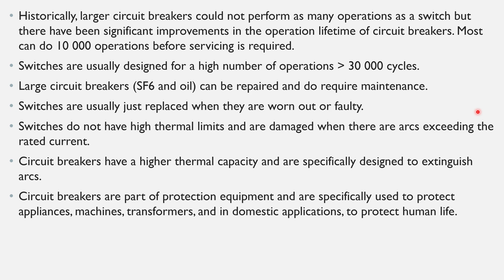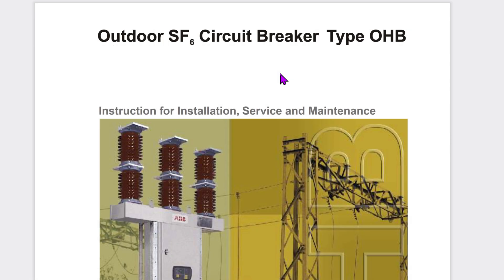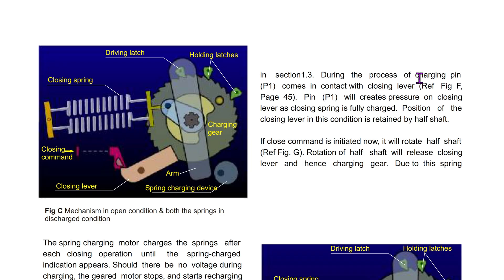Larger circuit breakers can be repaired and do require maintenance. This is particularly true for the sulfur hexafluoride, oil, and air blast circuit breakers. Looking at this SF6 circuit breaker manual, you can see there are a lot of moving parts including gears, relays, pins, actuators, and springs, and after repeated operations these parts need to be maintained.